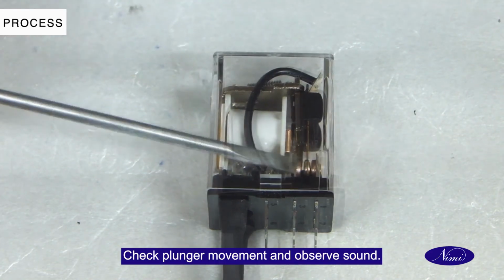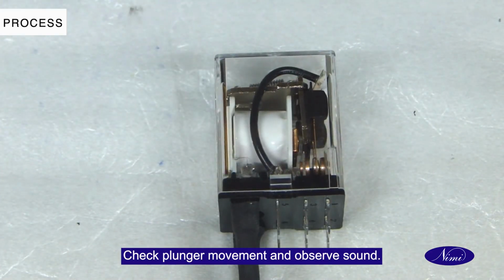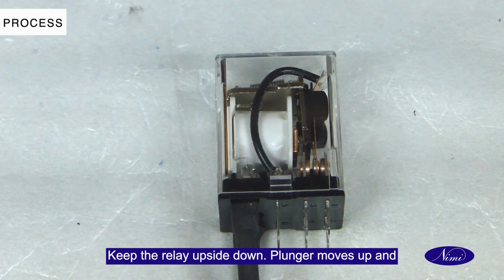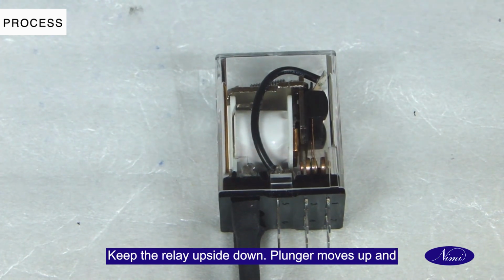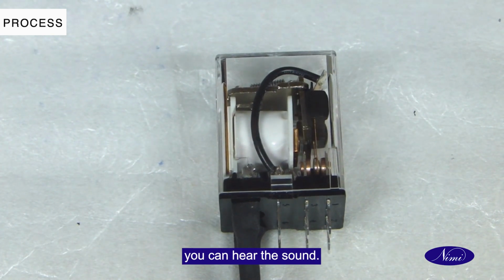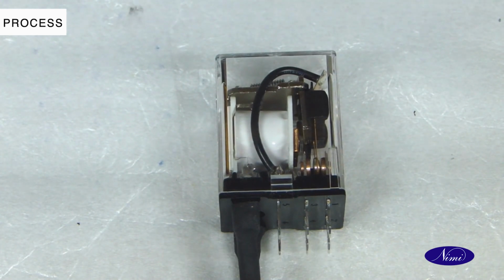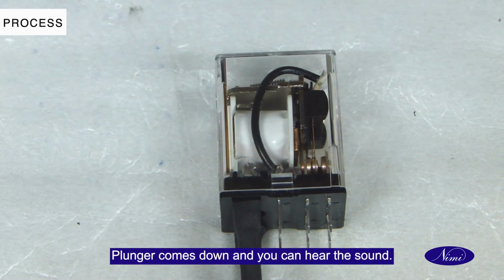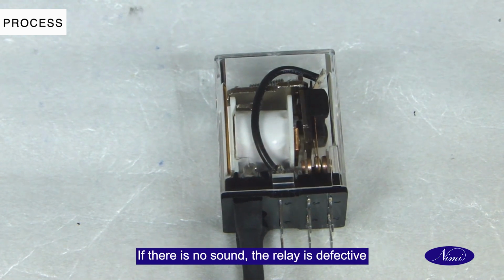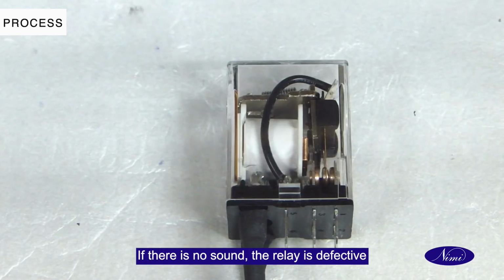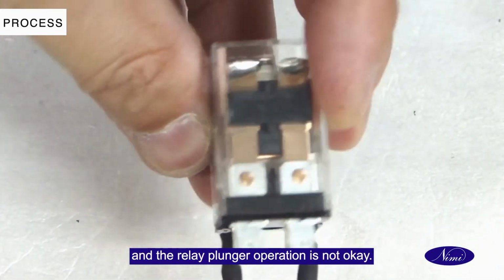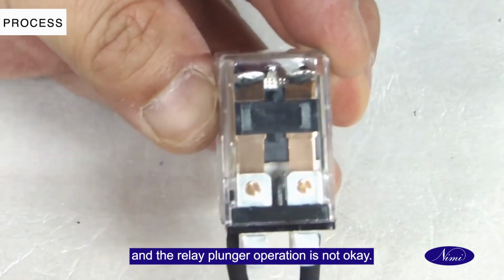Check plunger movement and observe sound. Keep the relay upside down. Plunger moves up and you can hear the sound. Bring it to the normal position. Plunger comes down and you can hear the sound. If there is no sound, the relay is defective and the relay plunger operation is not OK.